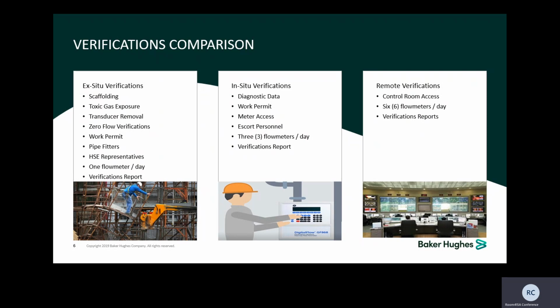These meters have transducers, and these transducers are pulled out. The thing is, these transducers are not easy to access. Sometimes you need to climb scaffolding. We had a customer who had the meter on the vertical flare side, 50 feet in the air, and they ended up calling us because one of their guys got hurt climbing that ladder. So it's a complicated way of doing it, but we've been doing it for a number of years.